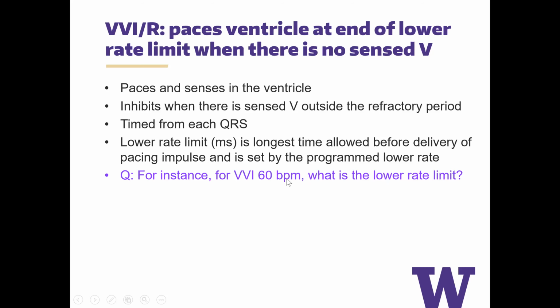It's just a little bit of math. If you started with 60 beats per minute, and you want to get to a number in milliseconds, because that's what the lower rate limit is, you would take 60,000, because there are 60,000 milliseconds in a minute, divided by 60 beats per minute. And so the lower rate limit in this case will be 1,000 milliseconds.